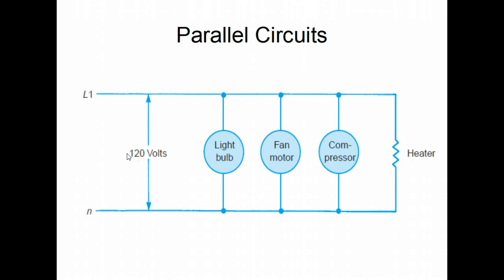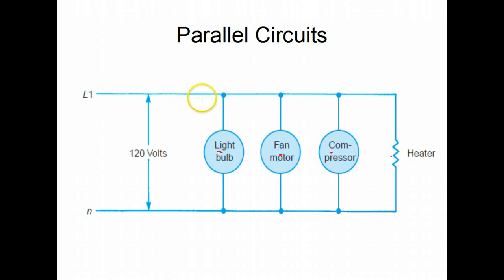Parallel circuits. Here's a basic parallel circuit — as you'll notice, we don't have any switches in it at this point. Parallel circuits are used for loads. The reason we have to have our loads in parallel is that each one of these loads — the light bulb, the fan motor, the compressor, and the heater — need 120 volts to operate properly. When you have a parallel circuit, you have a complete path to flow through the light bulb at 120 volts, through the fan motor at 120 volts, and the same with the compressor and the heater.